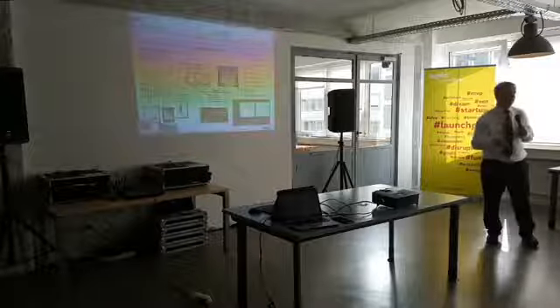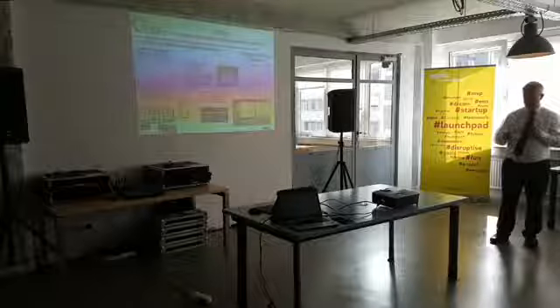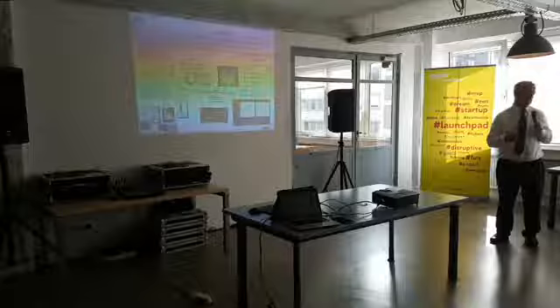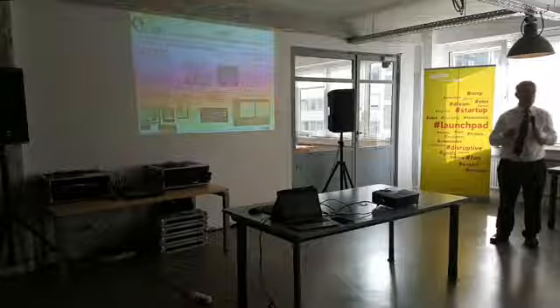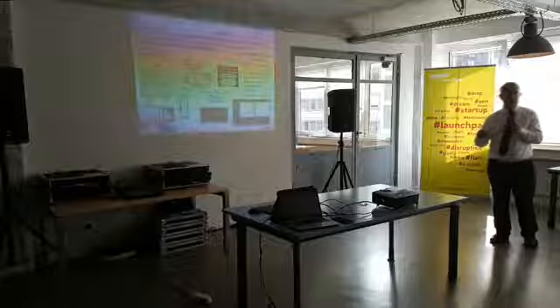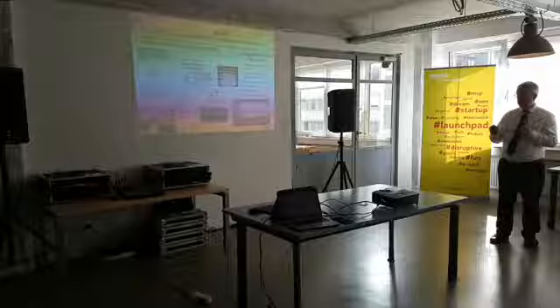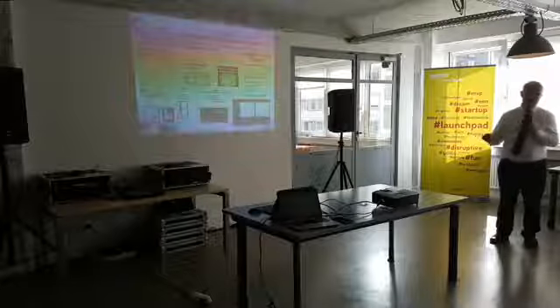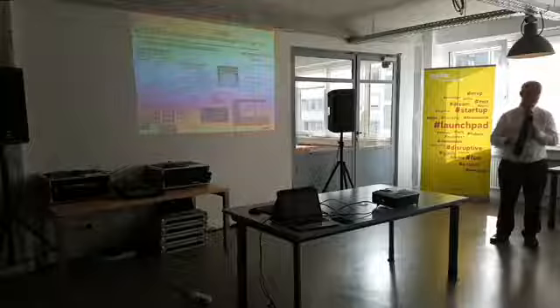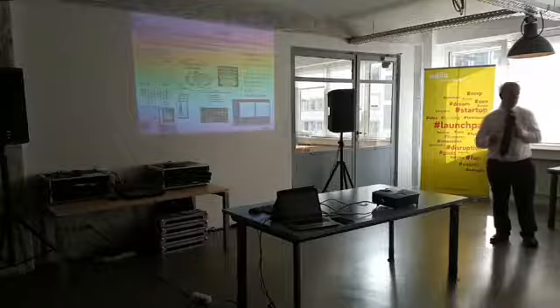Now this interworks with utilities' existing distribution management system, but what it does is put the operator as a human in the loop. So you can have a smart management system at both MV, and particularly at LV, which at the moment in most grids is very little monitored. And importantly, our solution is low cost and scalable, because, as mentioned earlier, it has to be low cost since there are a lot more monitoring points required.